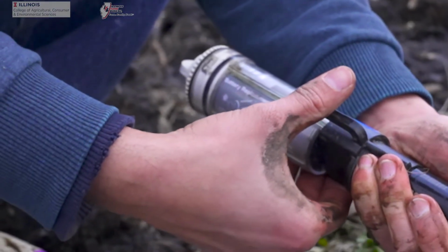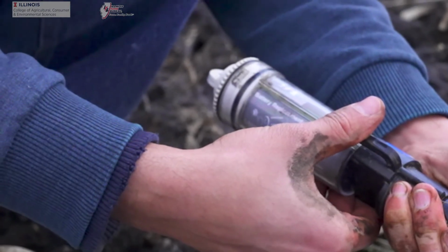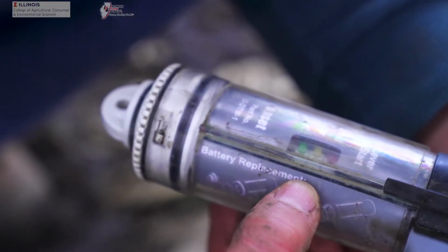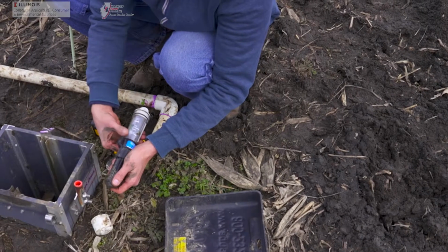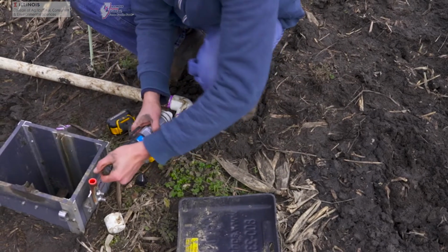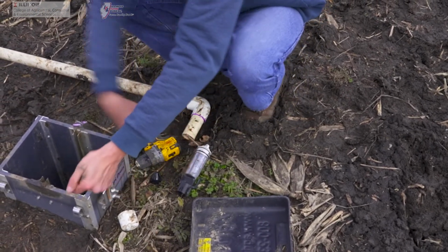Press the lever on the transfer shuttle and look for the yellow light to start blinking. This blinking yellow light means data is being downloaded to the transfer shuttle. The light will change to green if the download was successful. If the light goes from yellow to red, detach the sensor from the transfer shuttle and restart the process.